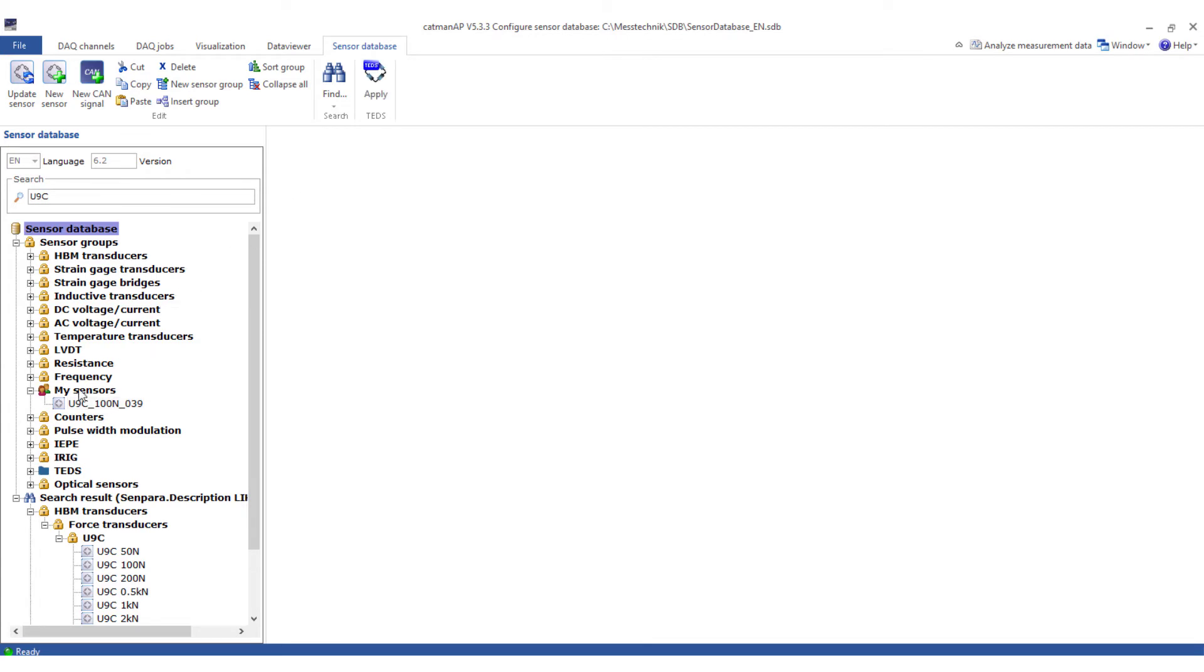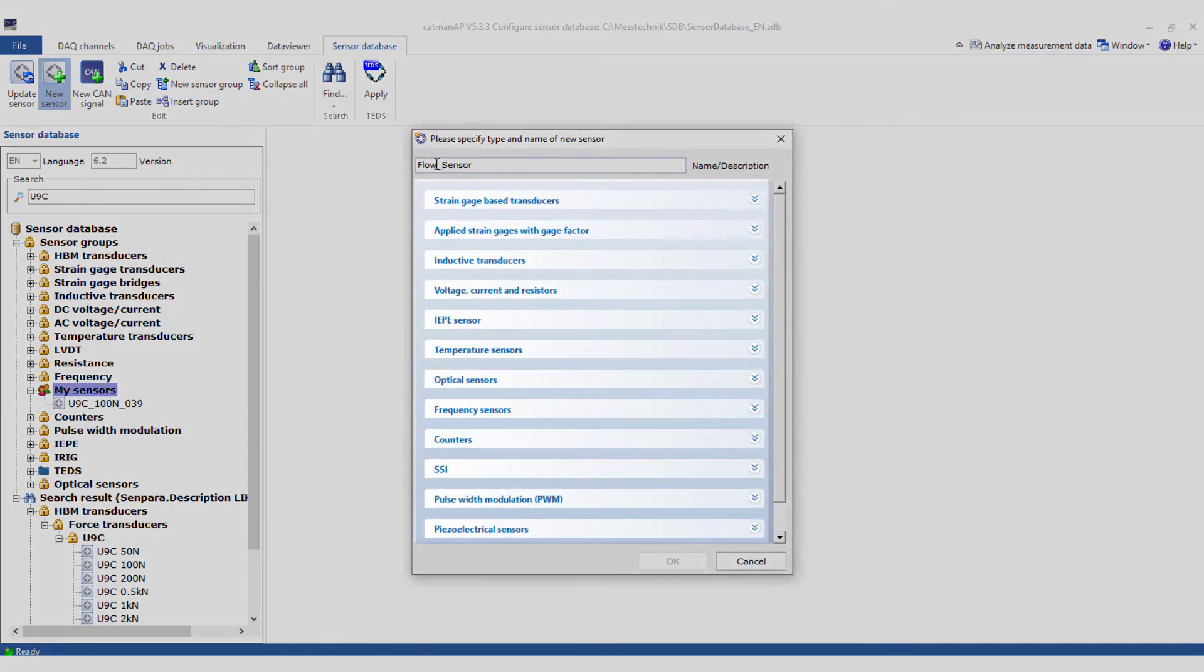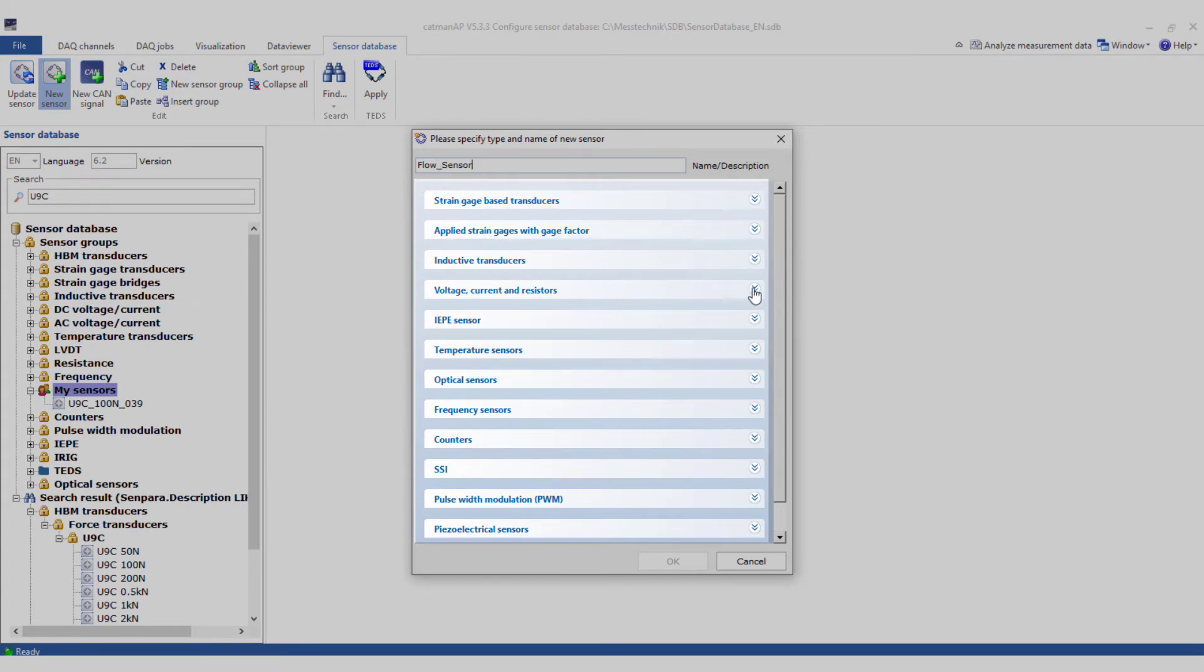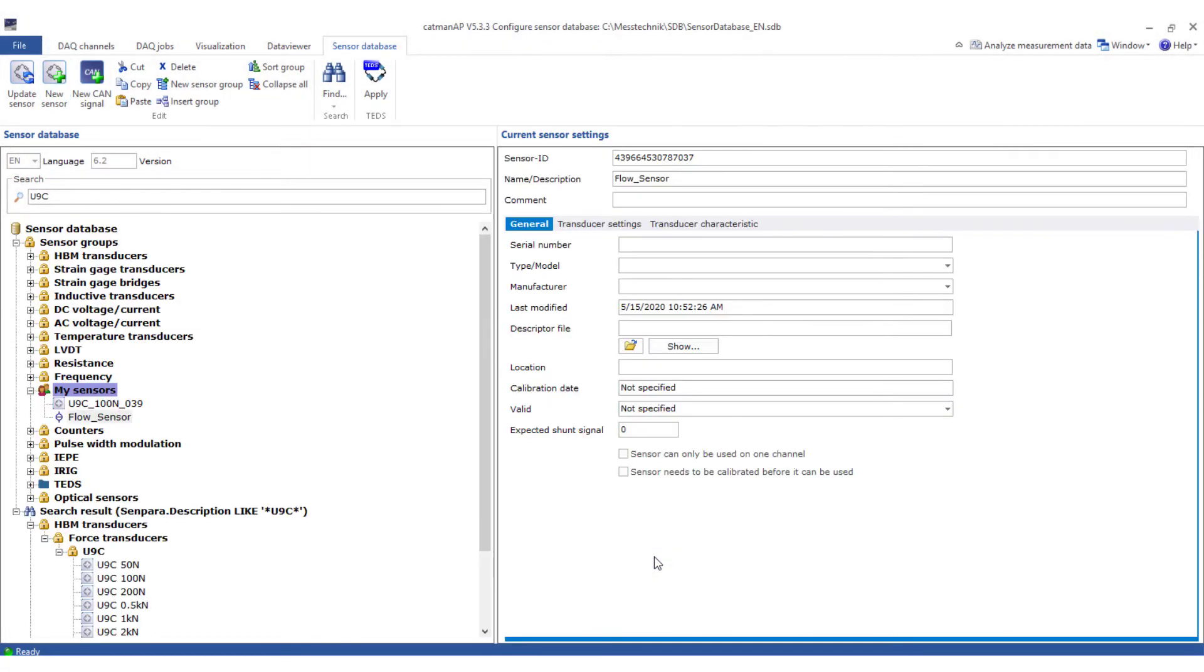How do you create such a sensor? Click on own sensors, new sensor, enter a name, and choose the type. Here it is not a matter of what the sensor measures, for example flow, but the electrical connection to the DAQ device is essential. Therefore current is the right choice here.